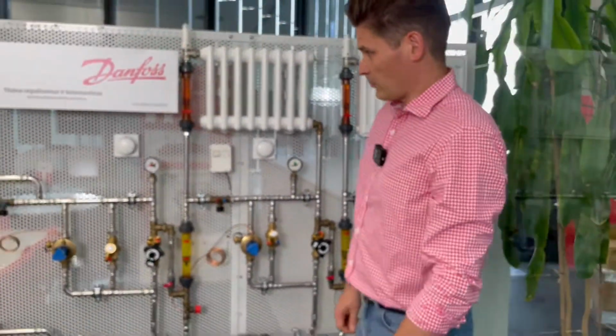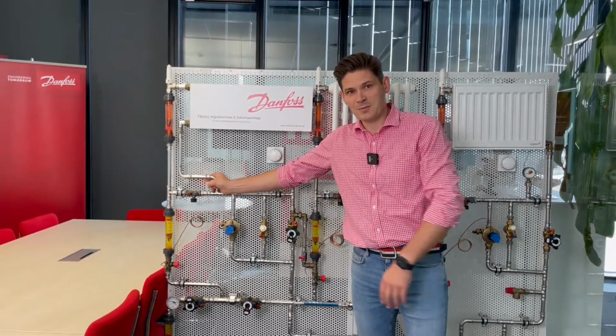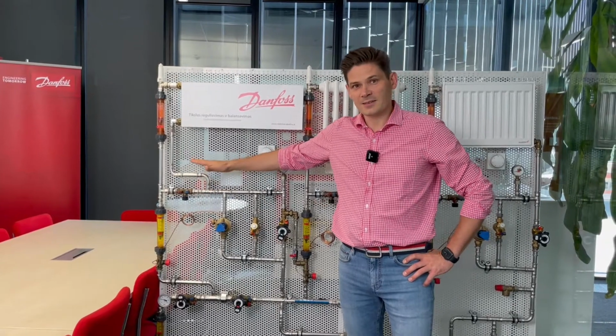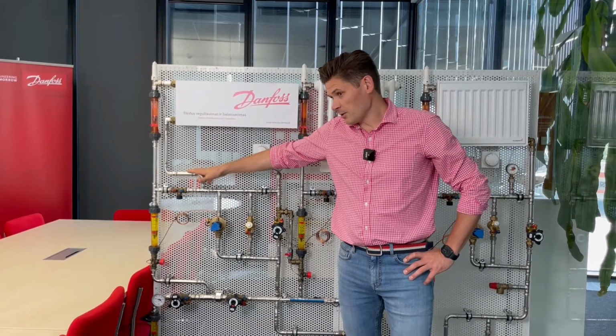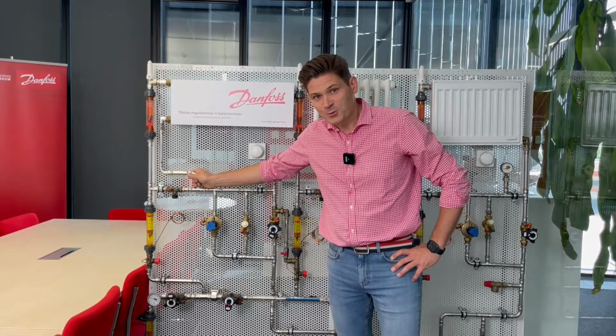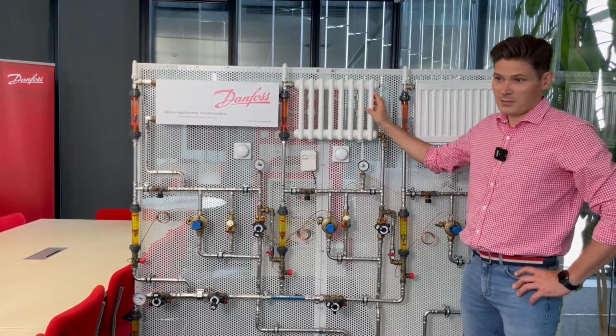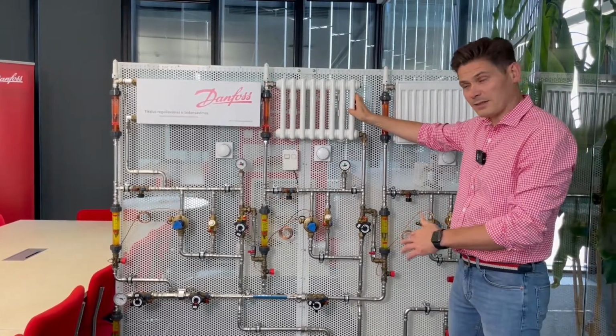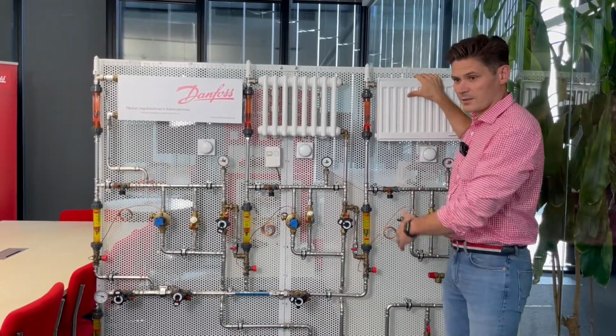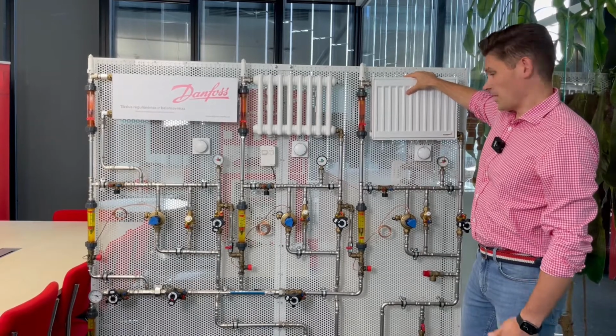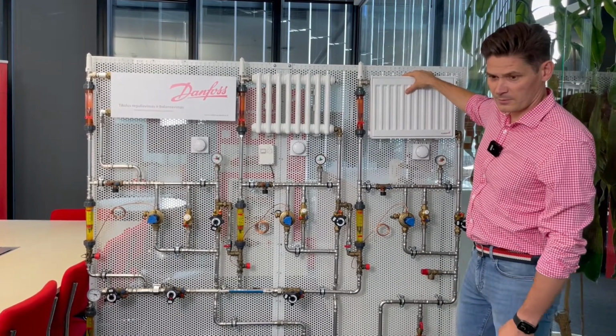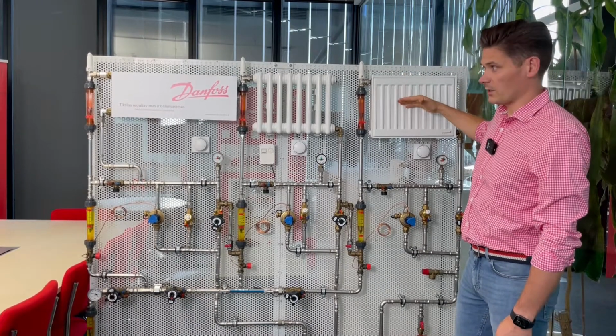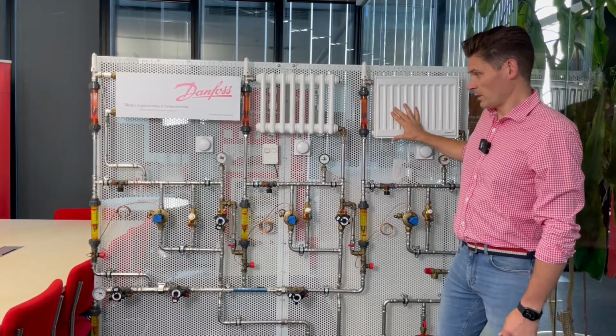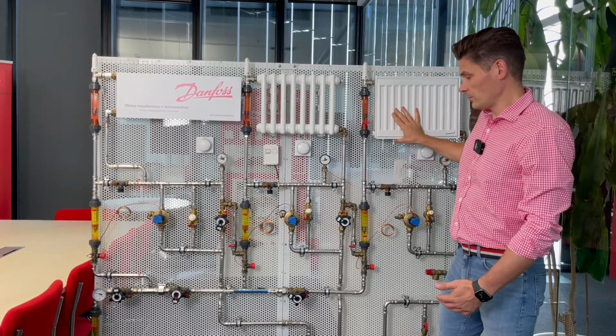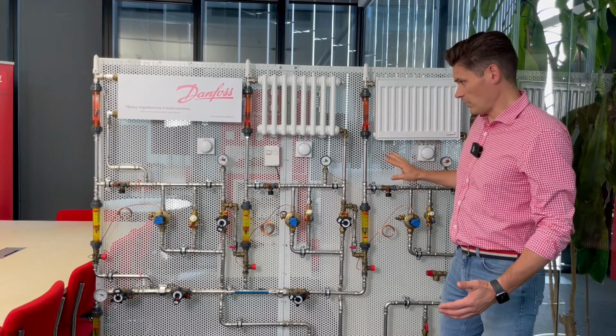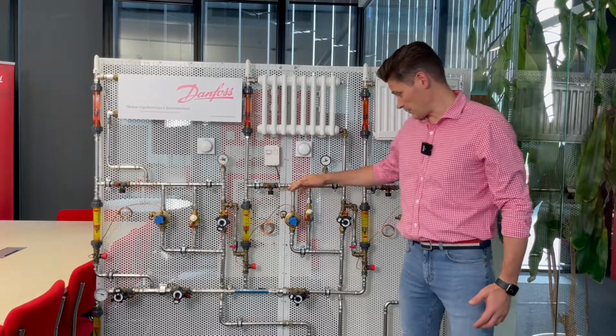People are happy. Of course, tenants in the first riser might not be so happy because they have less flow than they had, and now they need to shut their windows. The riser in the middle might not feel a big difference before and after balancing, and tenants living in the last riser, they are very happy because they have the designed flow and they have enough heating. So now all 3 risers are heating equally, and we have a constant flow static system. There is no regulation, only manual balancing valves installed.